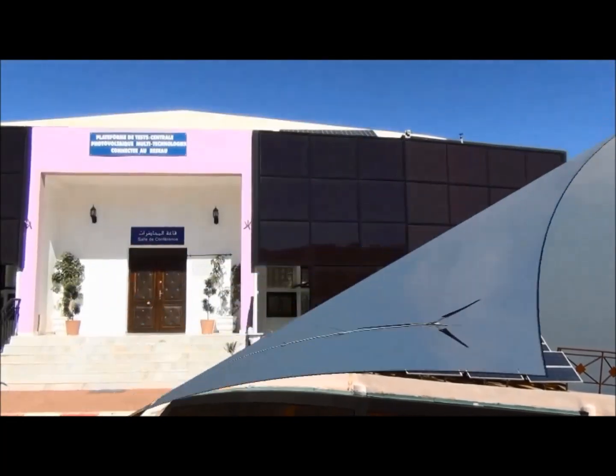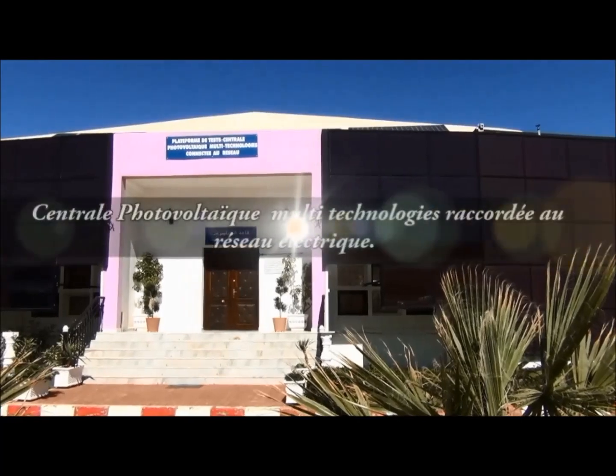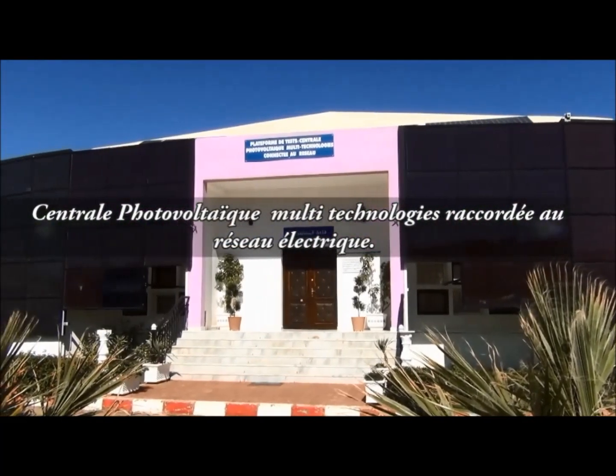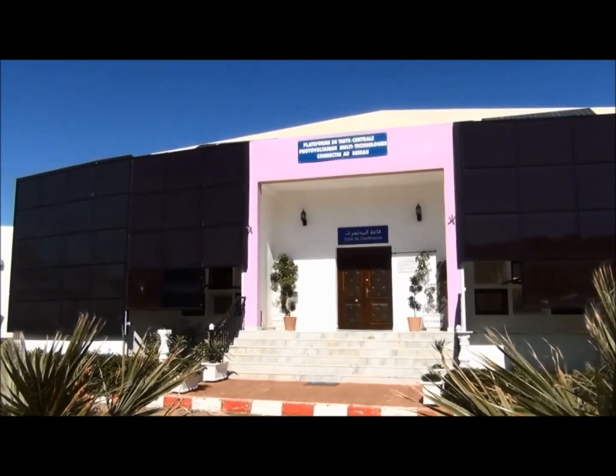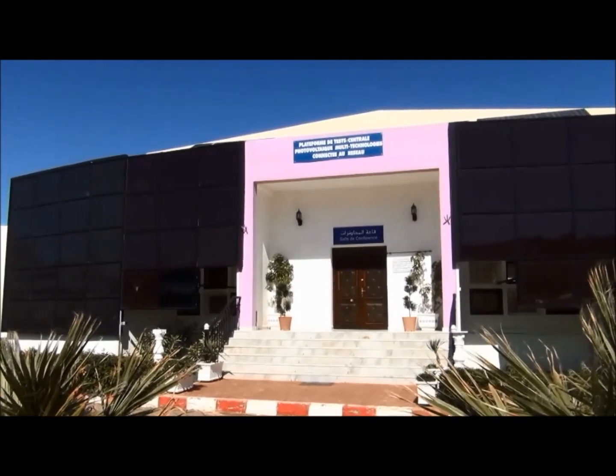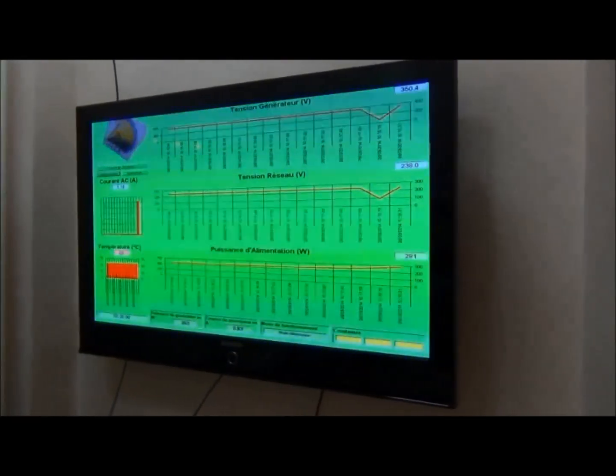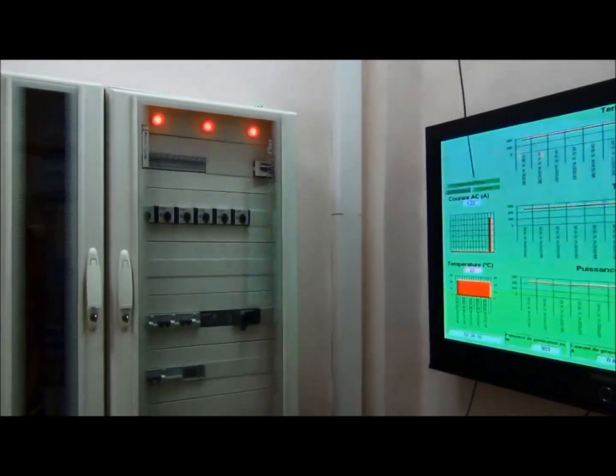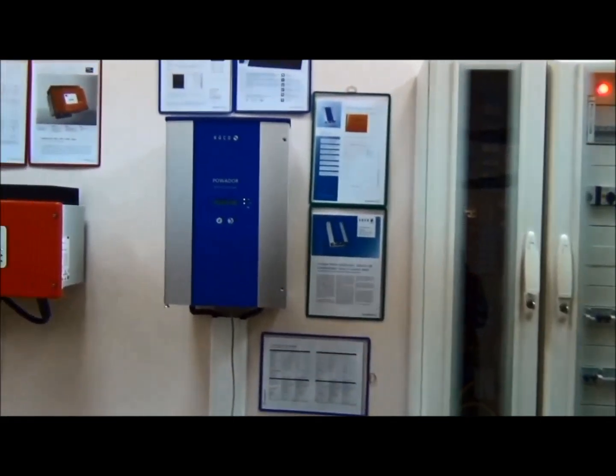The PV multi-technology pilot plant installed in UDES consists of 12.5 kilowatt peak photovoltaic fields of different technology. The monocrystalline and polycrystalline PV fields are installed on the roof of the building in a panel inclined to the latitude of the site, while the PV array using thin film modules are installed on the facades of the building. Each of these technologies contributes up to 2.5 kilowatt peak. The various PV fields are coupled to the grid through different PV inverters.